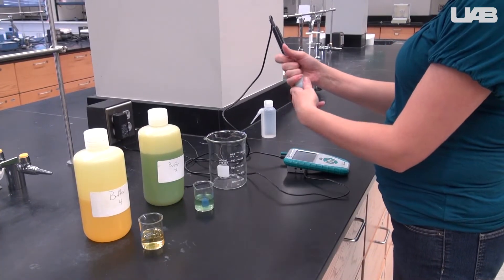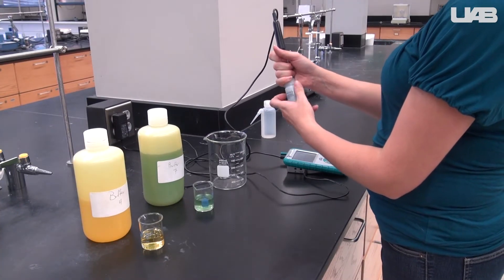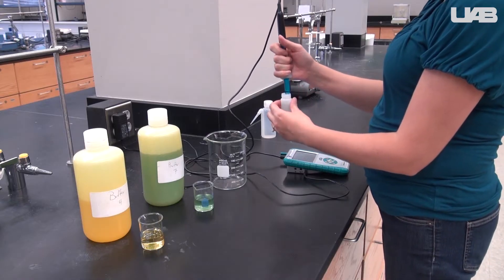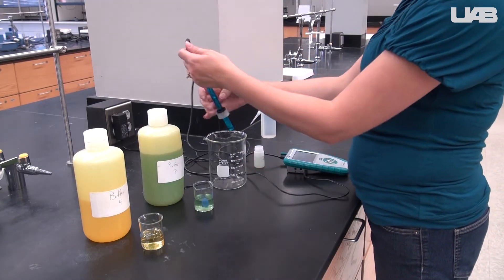Note the cap on the end of the pH meter. Do not remove the cap. You can push this up to the hilt, but if you remove the cap, you risk damaging the sensitive probe.